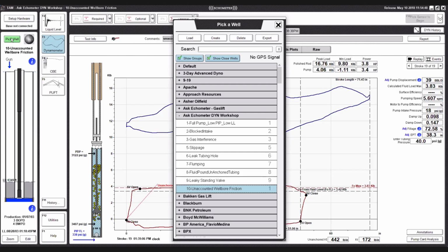It's important when you use the PRT that the polish rod is not being bent by misalignment, and that can tend to cause diameter changes that aren't representative of the fluid load pulling on the rod string. The other thing is that the PRT is sensitive to temperature change. So usually when Ken and I would go to a well, he would put the polish rod transducer on the well first thing and try to get it to acclimate to the temperature of the polish rod, and that would tend to make the data from the polish rod transducer not drift as much. And so if you see the minimum loads and the peak loads not being at about the same level with the PRT, then that's going to have an effect on the change in load, and it may look like the PRT is leaking when all it is is the temperature changing.